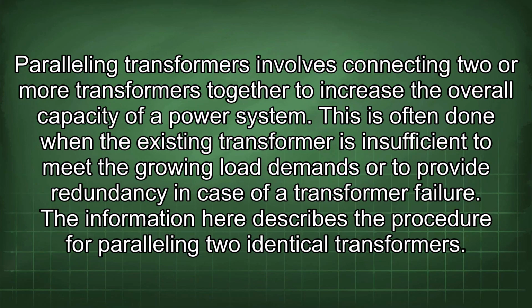Paralleling transformers involves connecting two or more transformers together to increase the overall capacity of a power system. This is often done when the existing transformer is insufficient to meet the growing load demands or to provide redundancy in case of a transformer failure. The information here describes the procedure for paralleling two identical transformers.